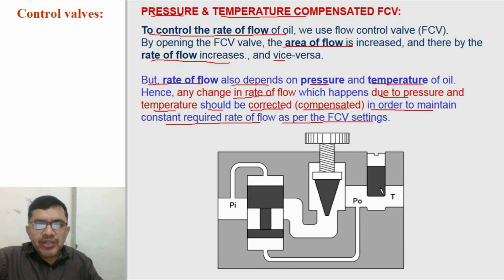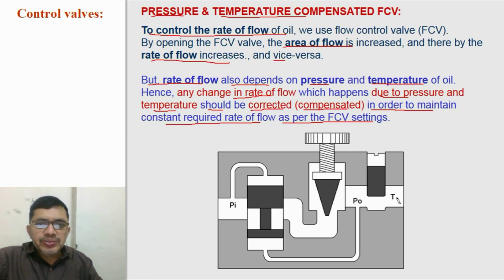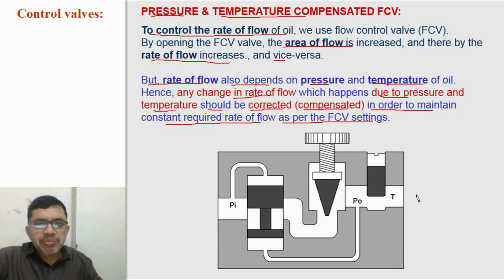And in the same way, if temperature of oil is increased, then viscosity will reduce due to which the flow rate will be slightly higher. So this variation in the flow rate due to pressure and temperature should be compensated. We need exactly 5 litres per minute rate of flow.